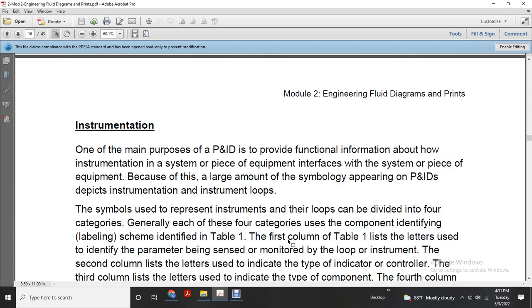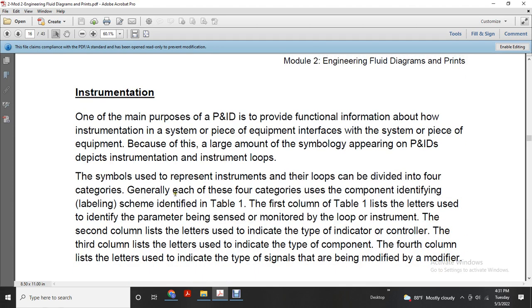Instrumentation. One of the main purposes of the piping and instrument drawings is to provide functional information about how the instrumentation system will interface with the piece of equipment. Because of the large amount of symbology appearing on the piping and instrument drawing to depict the instrumentation loop, symbols used for the reference of the individual instruments and their loops could be divided into four categories. Generally, each of these four categories is used for the component identified with the labeling scheme identified in Table 1.